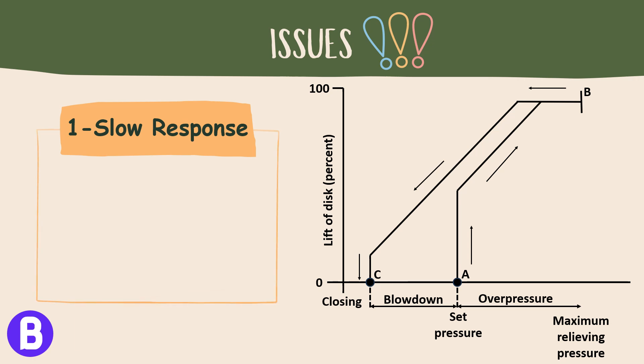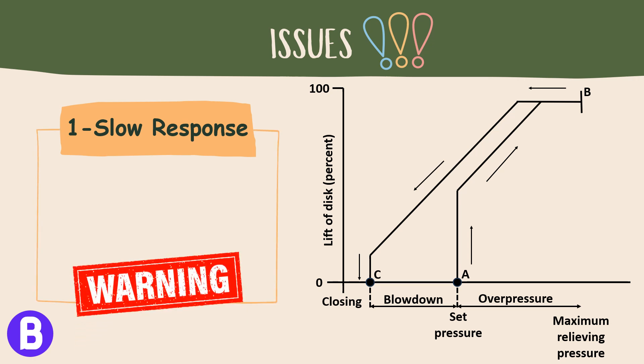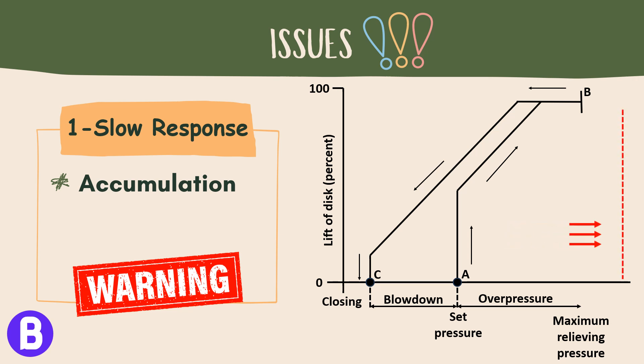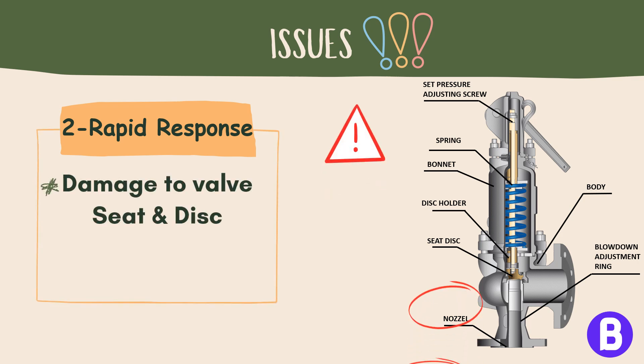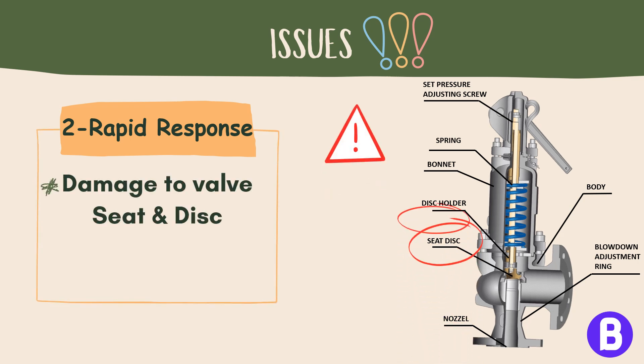These issues can include slow response against overpressure, not relieving enough fluid. This can lead to an accumulation pressure higher than required, meaning the vessel is subject to overpressure. Another issue is rapid response by opening and closing rapidly, which can lead to damage to the valve seat and disc — a phenomenon called chattering.